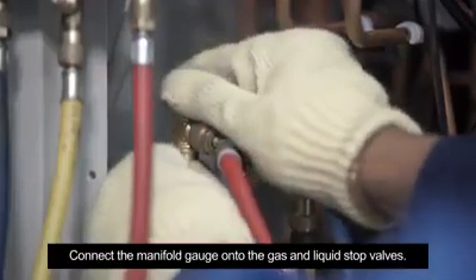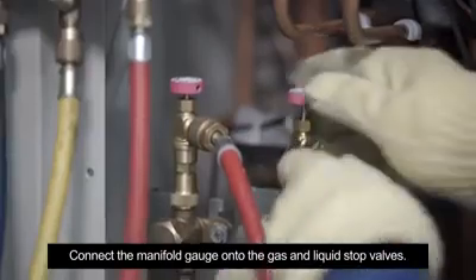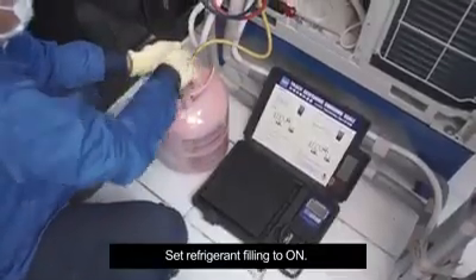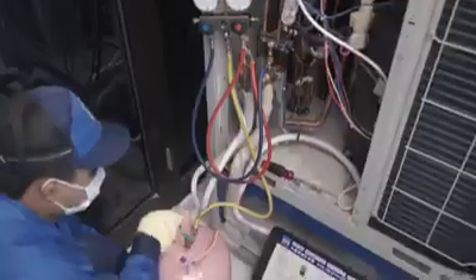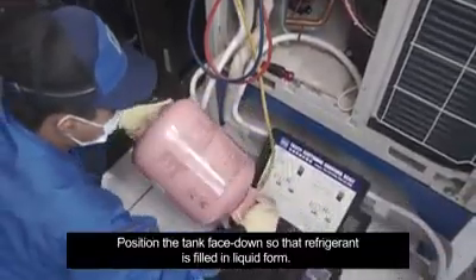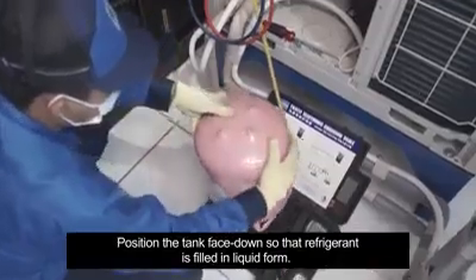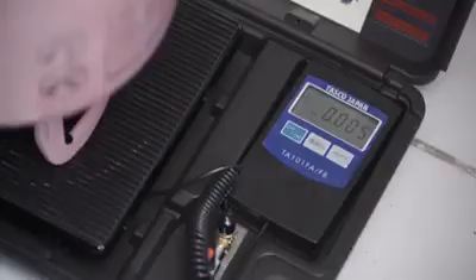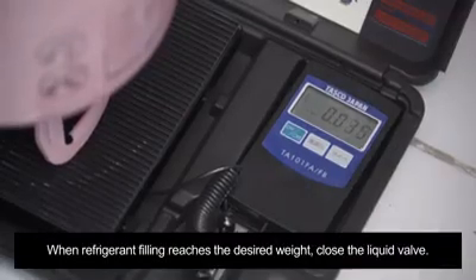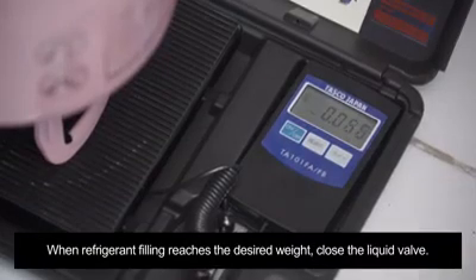Connect the manifold gauge onto the gas and liquid stop valves. Set refrigerant filling to on. Position the tank face down so that refrigerant is filled in liquid form. When refrigerant filling reaches the desired weight, close the liquid valve.